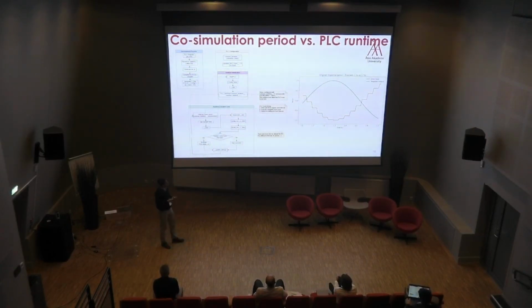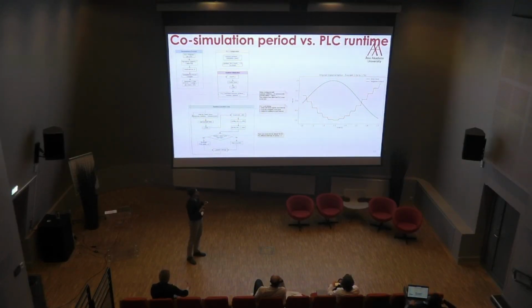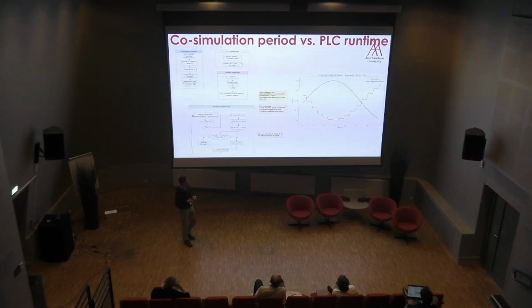Before the solution, what it produces is like this scenario here, where we have a simple inverter implemented with this approach. If we simulate that inverter, provide a sinusoidal sine wave input function, the output is stepped like this, because the time period of the co-simulation algorithm does not match the runtime period of the PLC program. In this case, the PLC program is too slow for the co-simulation algorithm. The co-simulation algorithm tries to provide new input, but the PLC program has not woken up yet. And when it wakes up, it sees another input and so on. So this mismatch of the periods is causing this trouble.